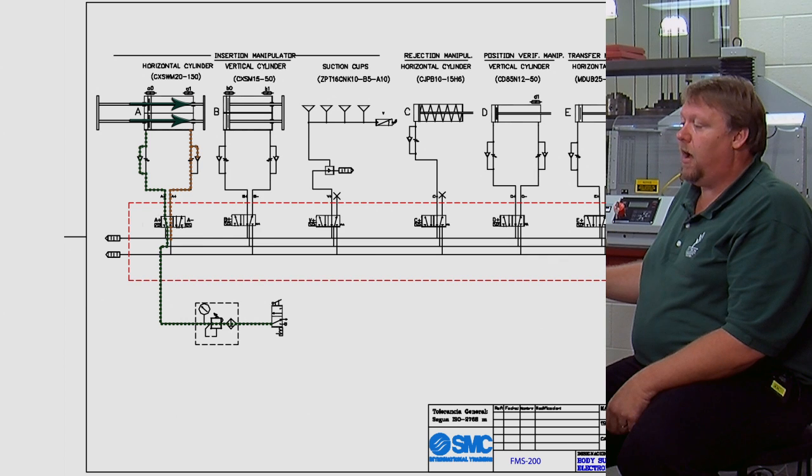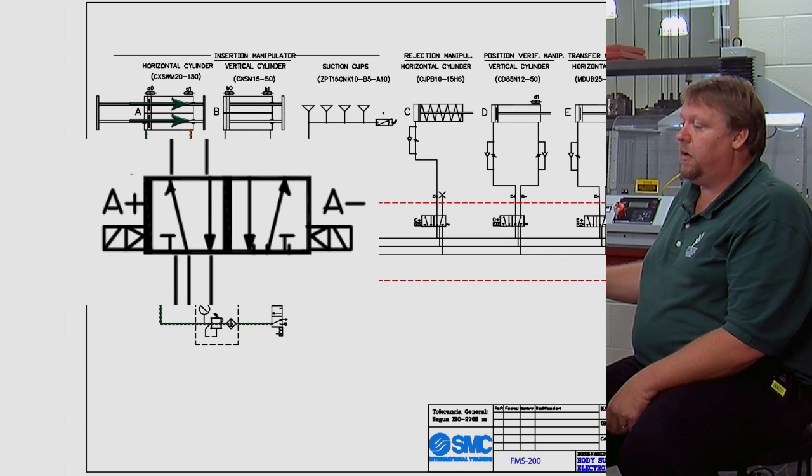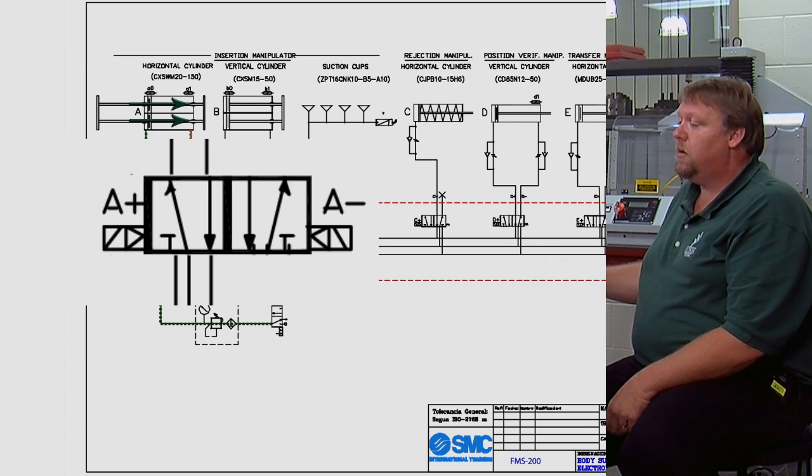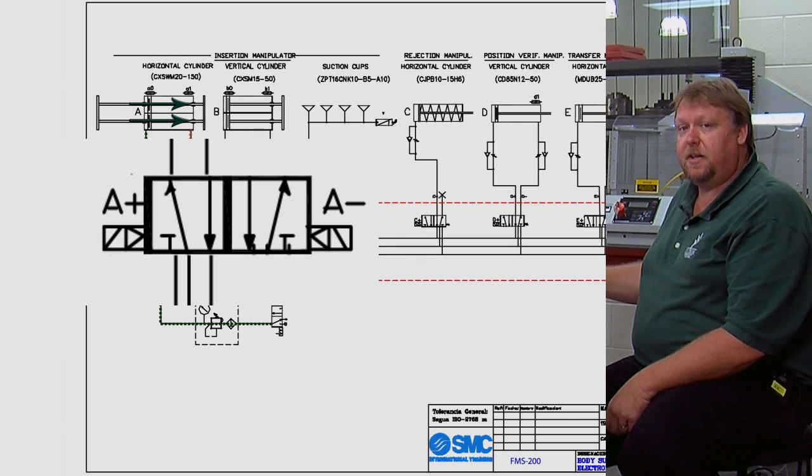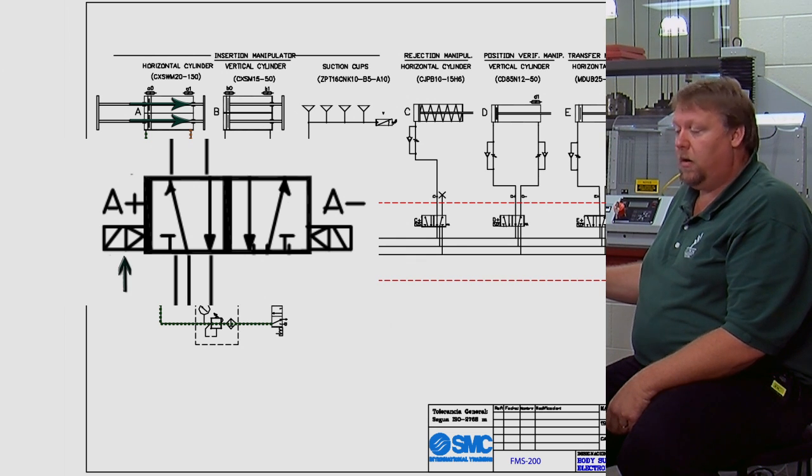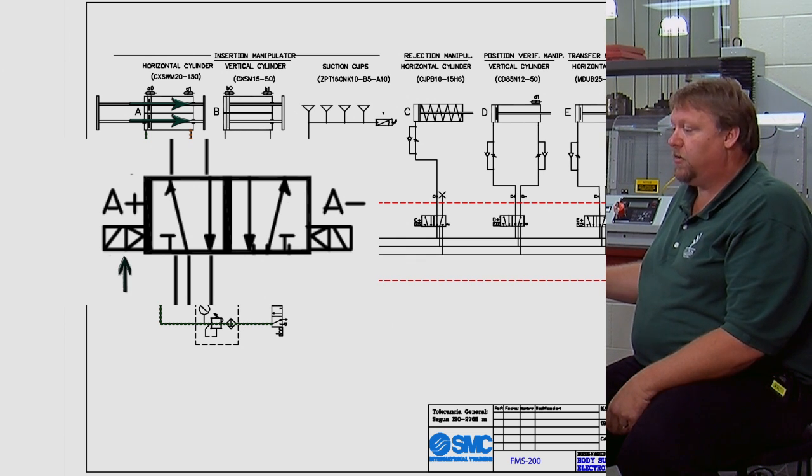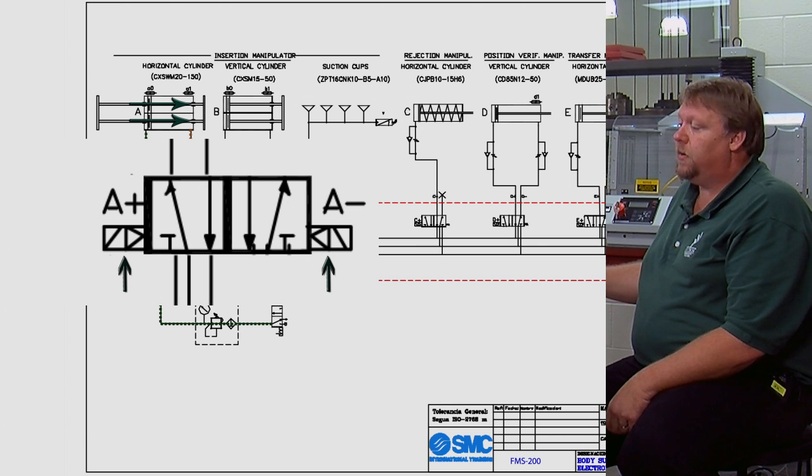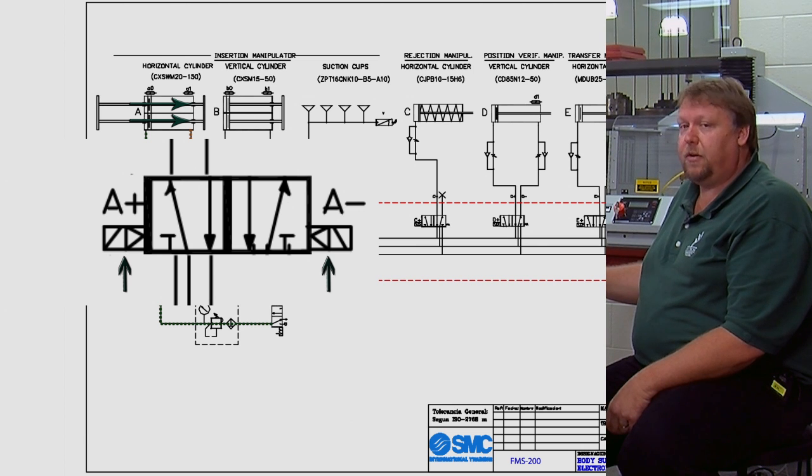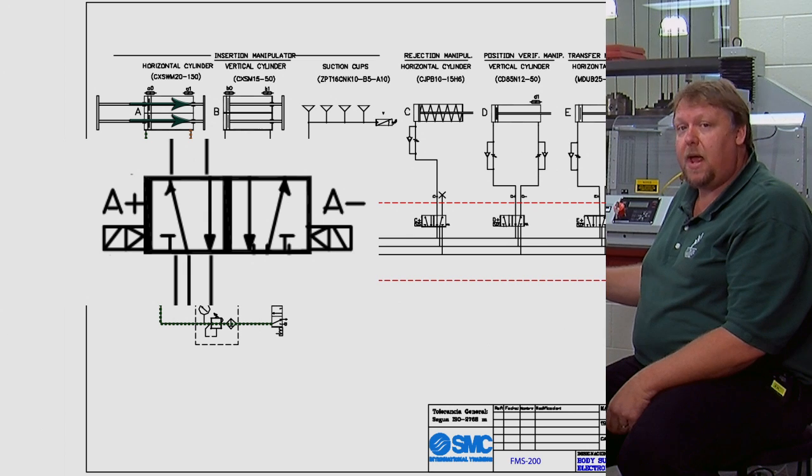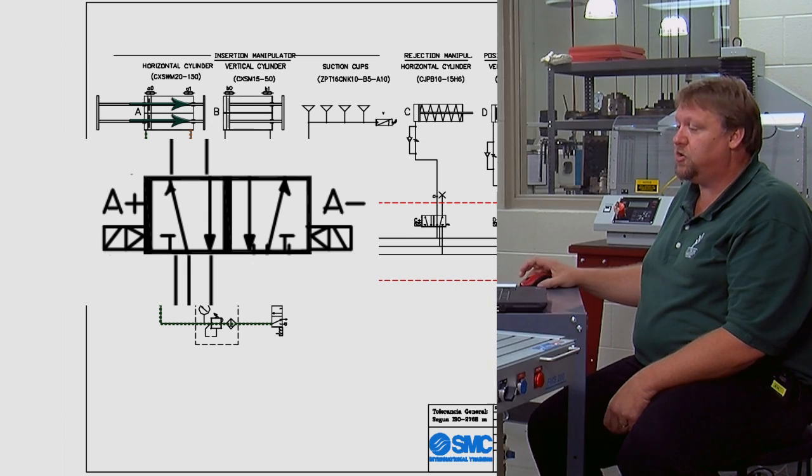Now this valve here is really important compared to all of the other valves because if we look at it we can see that it actually has two coils on it. We have a coil here and we also have a coil here. So it takes a signal to both extend and retract and it's going to remain in that position.